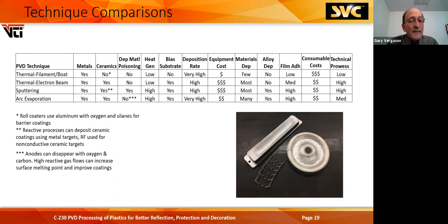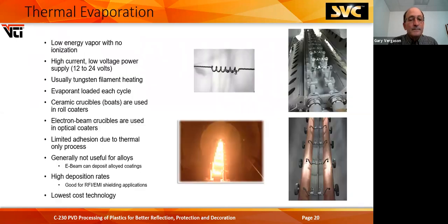Now, I'm not going to get into a lot of electron beam coatings, because those are primarily in the optical industry, where the parts are in planetaries over the top of the crucibles. So we're mainly going to be talking about the thermal filament-based coatings. Taking a little look at thermal evaporation, it's low energy vapor with little to no ionization.